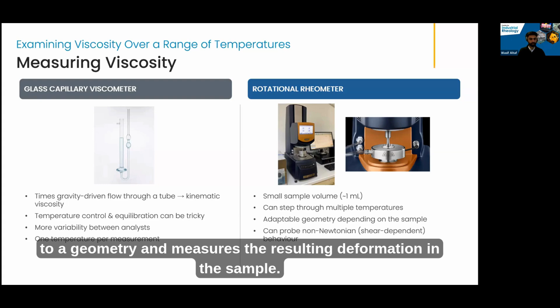With this method, temperature control and equilibration can sometimes be a little bit tricky, and there can sometimes also be some variability between analysts if you're just using this method alone. What we used in this study is a rotational rheometer. It's one of our 5 rotational rheometers that we have in the lab. Specifically, we used a TA Instruments DHR2. The basic principle of a rheometer is that it delivers torque to a geometry and measures the resulting deformation in the sample. For anyone more familiar with rheometers, in terms of the geometry used for these measurements, we used a 2-degree cone. However, we do have the ability to adapt the geometry depending on the viscosity of the fluid. So for example, in some cases, a concentric cylinder may be more appropriate.